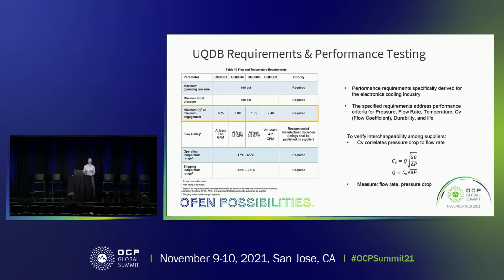CV is simply defined as the flow coefficient, and as you can see on the screen, it's defined as the flow rate of the fluid through the component times the square root of specific gravity over the pressure drop through that component. In this case, in the specification, this is defined with water, and our testing is done with water, so you can safely assume specific gravity is equal to 1, since specific gravity is defined as density of fluid over density of water.